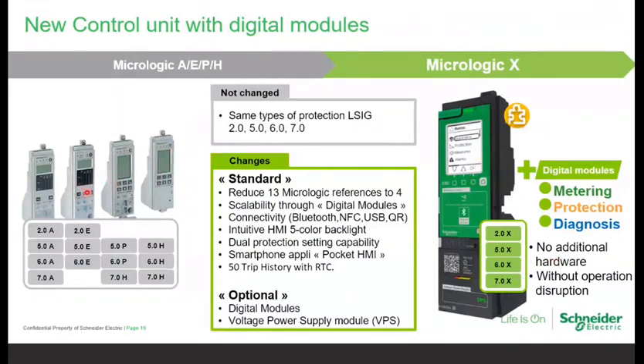So earlier in NW we used to have 13 references, let's say with basic protection LI, LSI, LSIG and LSIV, that is 2, 5, 6, 7, and there are 4 types of trip units AEPH. So these include 13 references. So we have straight away reduced all these 13 references to only 4 references. It means your MTZ breaker will come with 4 trip units only, that is LI, LSI, LSIG and LSIV. All other features are possible to upgrade by using the digital modules.